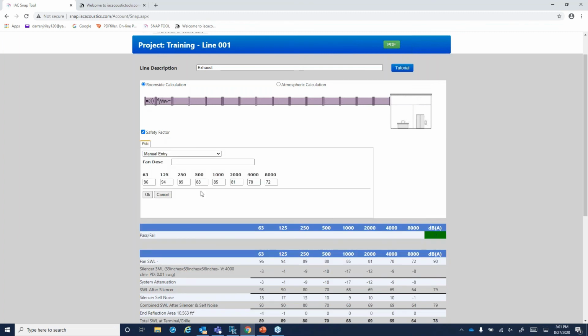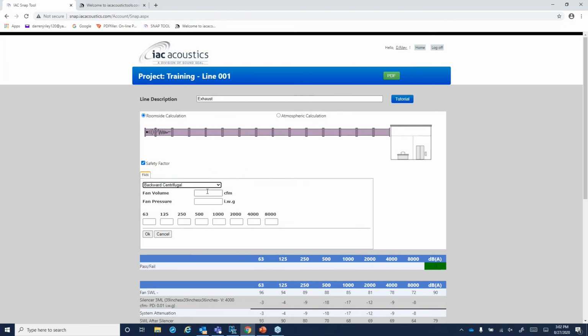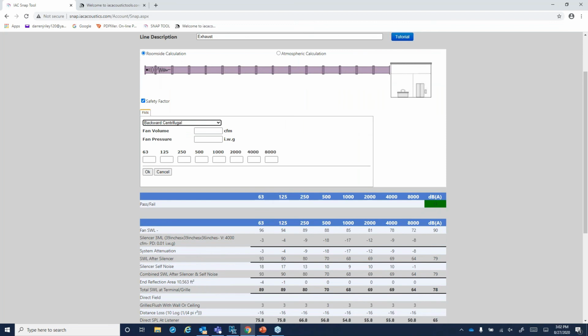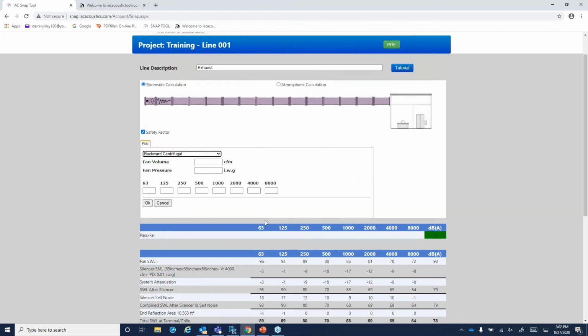The next thing you want to do is, if you have the fan criteria, the cut sheets, and they have the 8 octave bands, you can take those 8 octave bands, which I have done here, and put those into the actual tool. So now you've set the tool not only for the room performance, but also in coordination with the actual fan. If you don't have the fan, you can click on the manual entry pull down tab. We have multiple different ones through here. Let's say we go for backward centrifugal. You enter in your CFM and your inches water gauge, and it will populate the different octave bands for you. We are conservative on that. We've had this tool since 1970, so we've been able to acquire a lot of data, but that is where we're at right now.